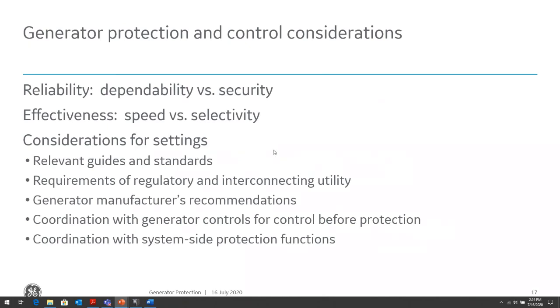So, consideration for settings. We'll talk about a lot of those considerations, but there are relevant IEEE guides and CIC guides that we can look at. There are working group committees within IEEE that came out with these guides, and we can look at the recommendations. We'll look at some of these guides at the end of this presentation. The generator manufacturer's recommendations, obviously the machine capability curve that is determined by the generator manufacturer, so we need to be operating within those curves. Coordination with generator controls and other control systems within the generation, and outside of the generator, the system protection functions. We need to coordinate with things outside the zone of the generator.